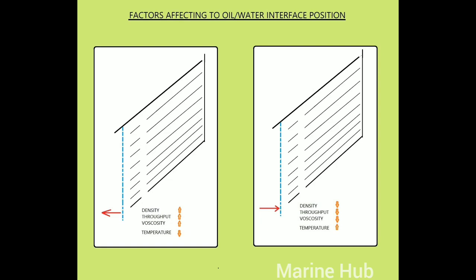If the oil-water interface moves towards disc stack more, there will be a risk of water escaping with clean oil outlet. If the oil-water interface moves towards outer edge of top disc more, there will be a risk of oil escaping with water outlet.